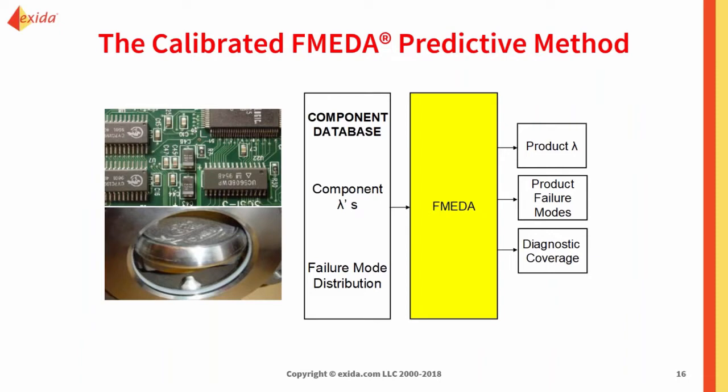When we do an FMEDA, we perform it on a very particular device. It's not just a floating ball valve. It is a particular company, a particular make, model, manufacturer, down to knowing exactly where it's going to go. Is it going to be a subsea device? Is it going to be protected and cabinet mounted? And what environments will it see? We detail every failure mode that's given in that component and the design for all the stress levels that design could see, including the environment.